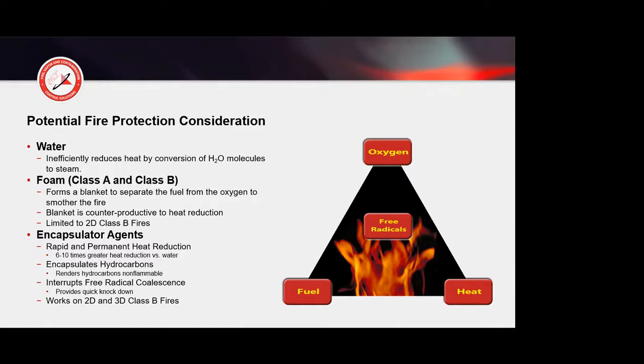That's why in the UL 162 test, which is your foam qualification test, not only do you put out the fire, but you're subjected to a burn back resistance test, because you haven't lowered the heat below the auto ignition temperature of the fuel. So you have to maintain a good separation to keep vapors from coming up, or they'll reignite from the heat still in the steel pan. Also, we see that it could be limited to two-dimensional class B. In fact, when we go to the NFPA 11 standard, it specifically states foam is not suitable for three-dimensional class B flowing fuel fires.